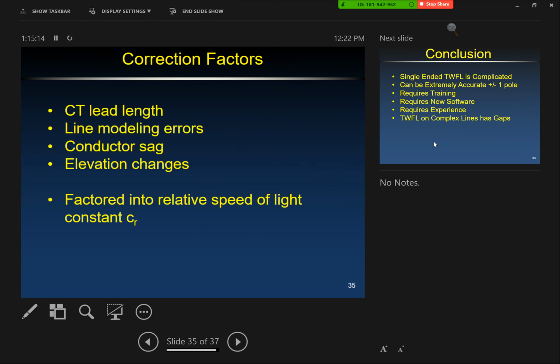Here I'm just going over some other correction factors: CT lead length, line modeling errors, which will get you if your GIS is off, conductor sag which we've talked about, and elevation changes. Most of these really just factor into your relative speed of light constant, unless it's really inconsistent in parts. If it's evenly spread over the length of the line, we didn't see any reason to worry about it.